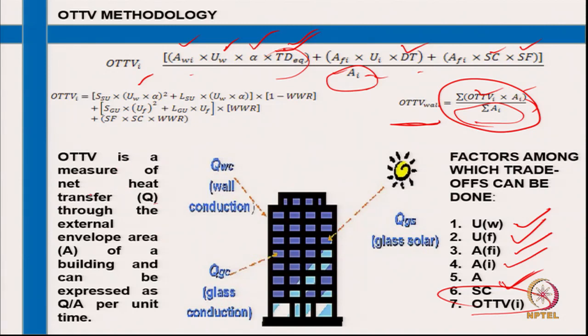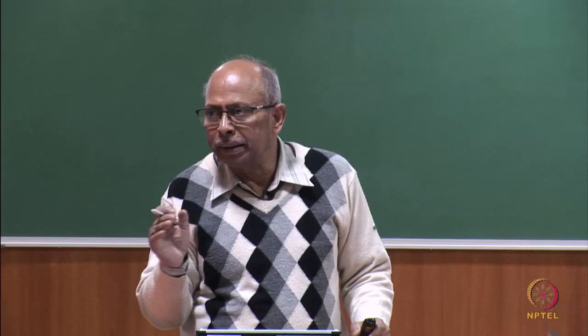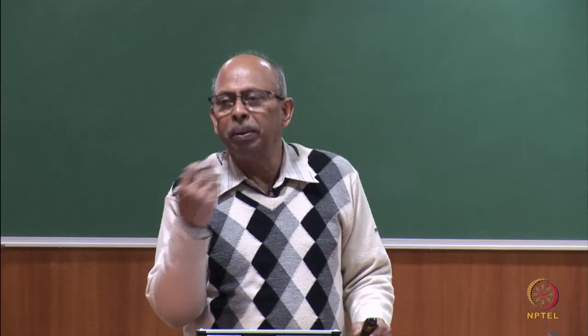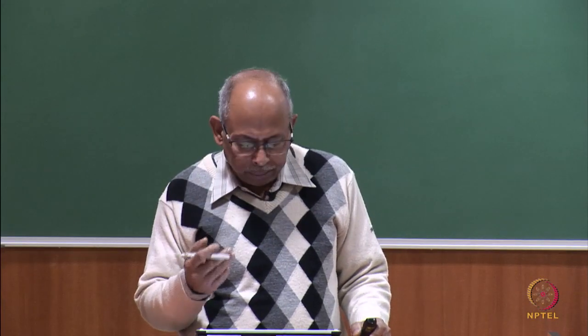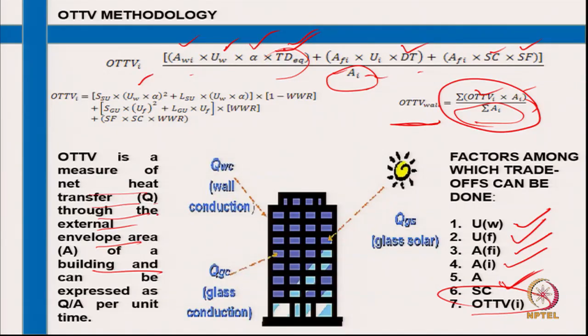So it is a measure of net heat transfer through the external envelope area of the building, expressed as Q by A per unit area. That means you sum up for each component in the envelope multiplied by their area, divided by total area of the envelope, giving you quantity in kilowatt per meter square or whatever unit.